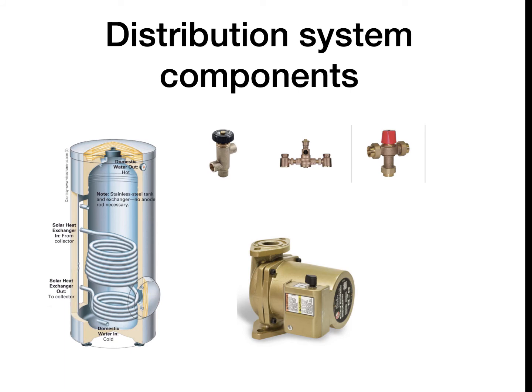These components are the required minimum components for a domestic hot water distribution system. You have the domestic hot water storage tank, also known as the indirect or the reverse indirect. You will have a point of generation anti-scald tempering valve. You could possibly have a point of use anti-scald tempering valve, and then you should have a domestic hot water circulation system if the source and the load have more than 25 feet of separation between them.